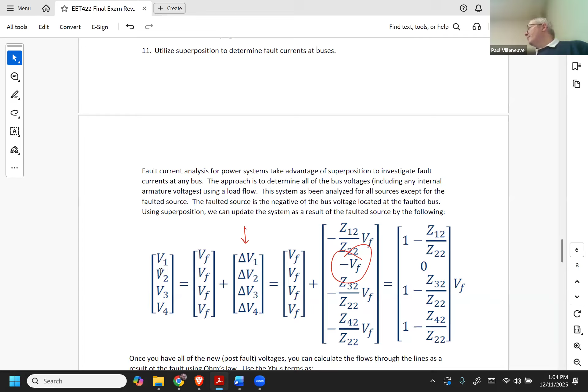And then that's the concept of superposition. And so when you add in a new source, you no longer have necessarily current, but you have changes in voltage. That's the whole thing about superposition, right? You're going to go ahead and calculate what they are one at a time, and then you add them all up at the end. This one is solving for the change in voltages because we've done all the other voltage sources in there. We just have to add that one that's indicative of the fault. And our change in voltages are going to be determined by our Z-bus. So those Z's that you see here are just grabbed directly from Z-bus. Now you can calculate line flows. So any line flow, you take the differences in voltages and you either multiply by the transfer admittance or you divide by the impedance between the two buses. That's all it is. That's exactly what we did on the first homework and the first test. We just keep doing it because it helps us calculate the current.